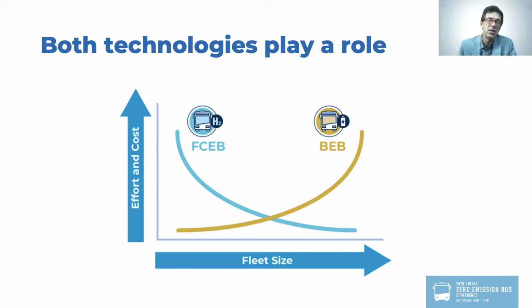Battery electric buses aren't quite as simple as just adding a charger per bus as you grow. If you have a bus yard in an urban area with 150 buses parked and fueled at night, you'll need to expand the infrastructure to support that load. For 5 buses, your existing transformer switchgear may be sufficient, and maybe up to 20 or 25 buses, but at some point you'll need to increase capacity at the station, and that can be quite costly, especially for 150 to 200 buses. You're basically putting in a substation in an urban area, and the cost actually goes up per bus on the price of the bus.